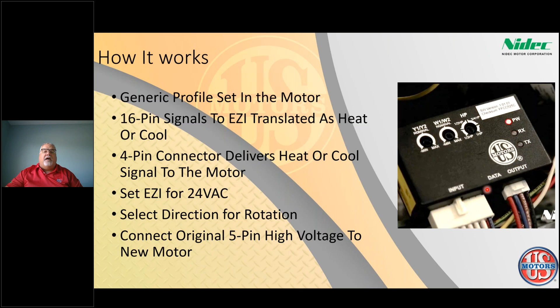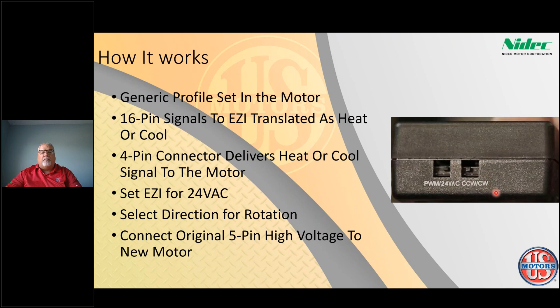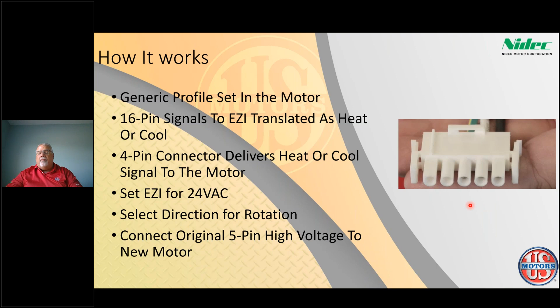So the 16-pin connection goes in. It decodes the signal, meaning it knows which speed taps are used for cool, which is Y1, Y2, and which ones are used for heat, W1, W2. And then we can set our horsepower. Once we've done that, we want to check and make sure we're set to 24-volt signals here on the side of the box. Then we select our direction of rotation, which will be on the blower housing as well, so you'll be able to select which rotation we have. And then lastly, we're going to connect the original 5-pin high voltage connector that came from the original motor, coming off the control board, right into the motor. So it's really as simple as that as far as getting the motor wired.